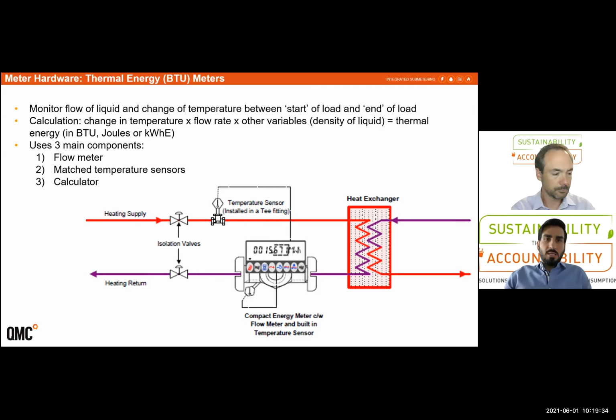Thermal meters, as most of you are familiar with, use 3 main components to calculate thermal energy: a flow meter measuring liquid volume, a matched pair of temperature sensors measuring the temperature difference between the beginning of the load or supply and the end of the load or return, and a calculator. Next slide, please.